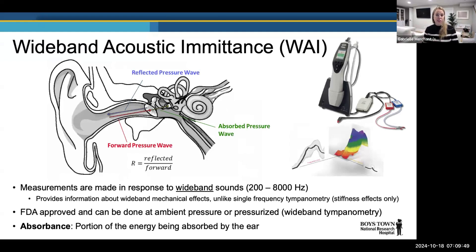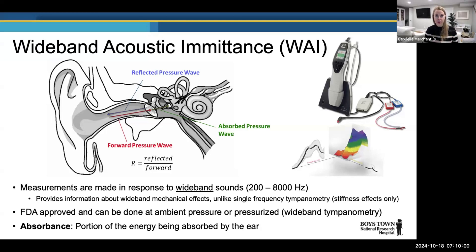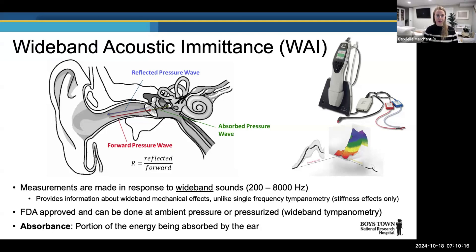The one measurement I'll assume less familiarity with is wideband acoustic immittance — a more comprehensive variation of our standard immittance measurements. Standard tympanometry is made in response to single-frequency pure tones, usually very low-frequency around 226 Hz, providing information really about the stiffness effects of the underlying mechanics. In contrast, wideband measurements provide information about wideband mechanical effects — stiffness, mass, resonance — giving a much more comprehensive picture of what's happening mechanically in the ear across frequency.